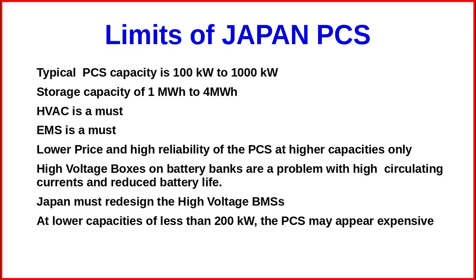One, the typical PCS capacity is 100 kilowatt to 1000 kilowatt. Storage capacity limit may be 1 to 4 megawatt hour. HVAC is a must. EMS is a must. Lower price and higher reliability of the PCS is possible only at higher capacities. The high voltage boxes on the battery banks are a problem, with high circulating currents and reduced battery life. This problem of course is there for both Japan PCS as well as for China PCS at higher capacities. So Japan must redesign the high voltage BMSs. At lower capacities of less than 200 kilowatt, the PCS may appear expensive.